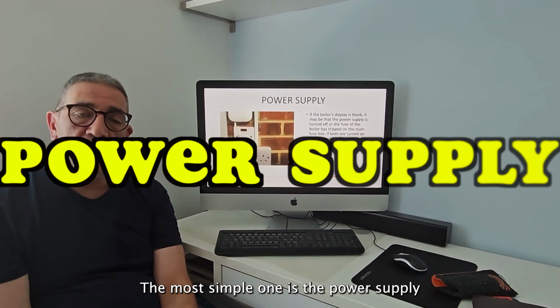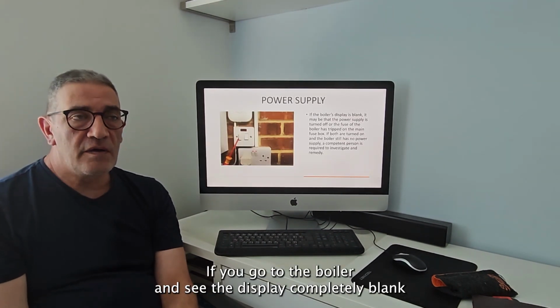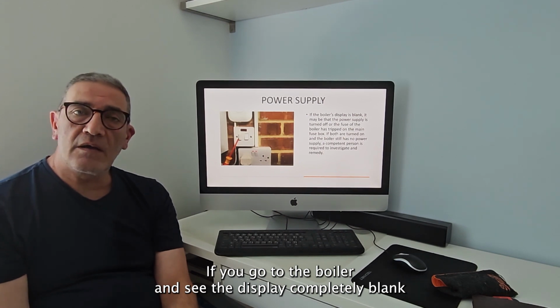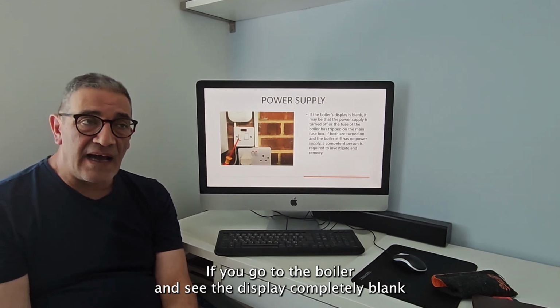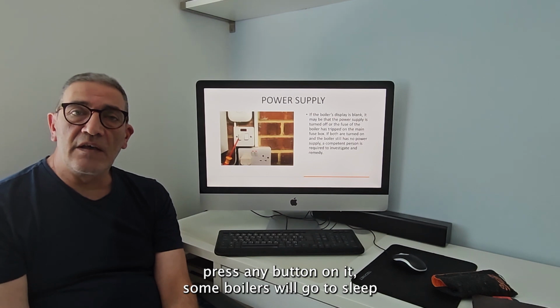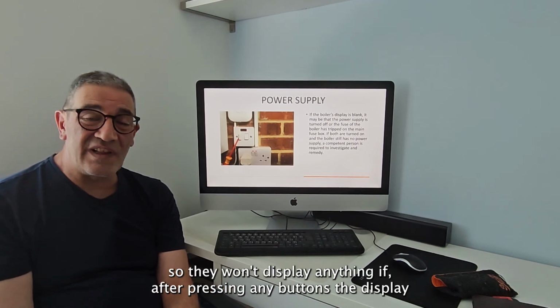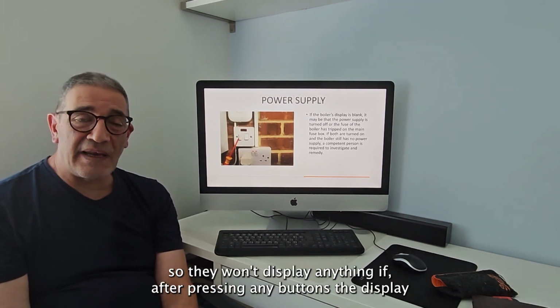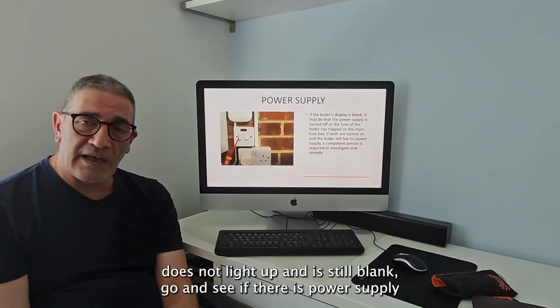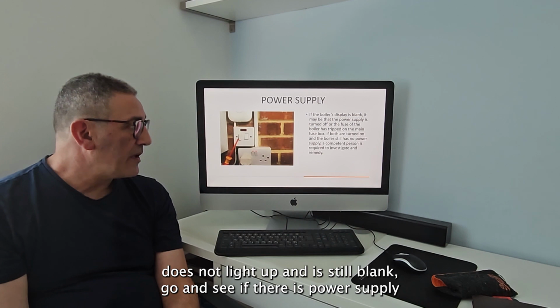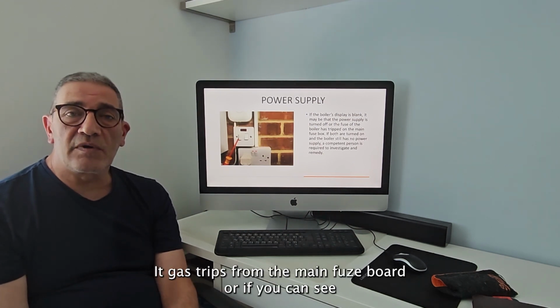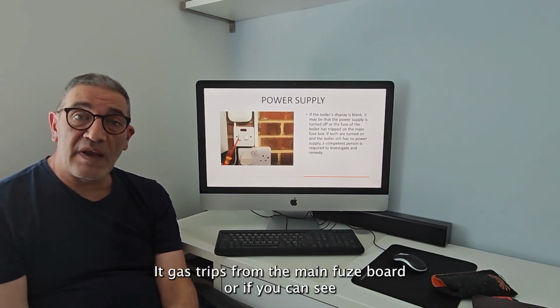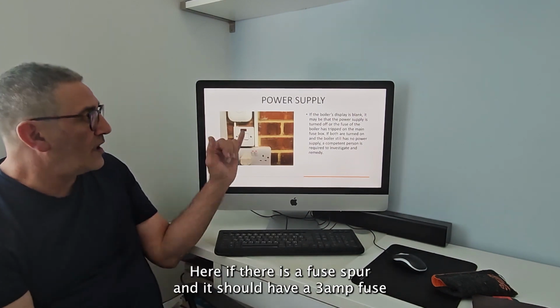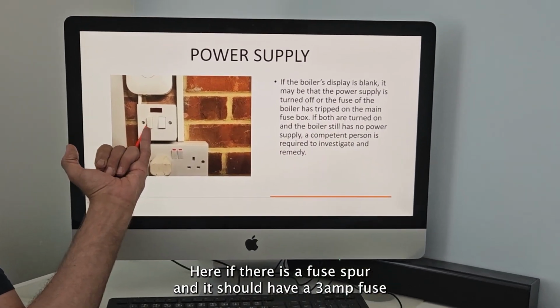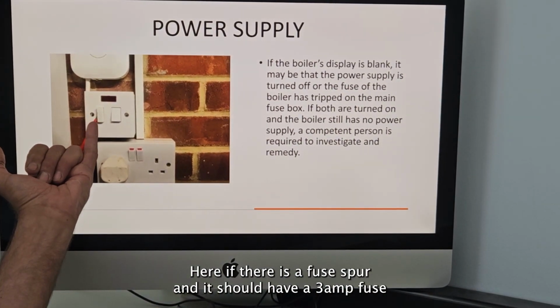The most simple one is the power supply. If you go to the boiler and see the display completely blank, press any button on it. Some boilers will go to sleep, so they won't display anything. If after pressing any button the display does not light up and it's still blank, go and see if there is a power supply. It has tripped from the main fuse board, or, if you can see here, there is a fused spur and it should have a 3-amp fuse.